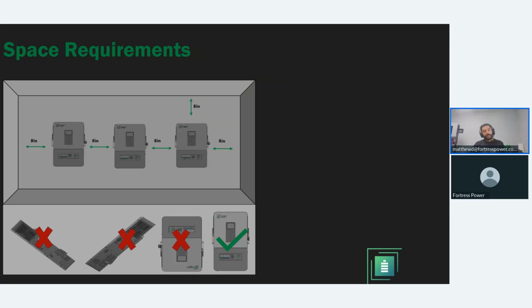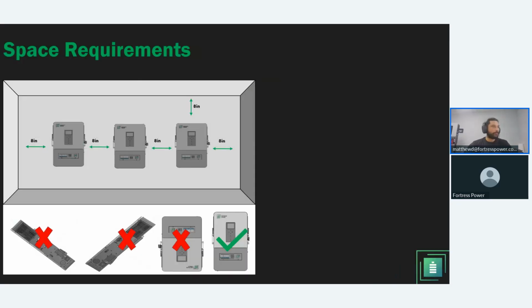All right. One thing we are going to require, and that's more for better heat dissipation, will be that each inverter is spaced 8 inches apart, assuming you're installing multiple of them. Again, reminder that you can do up to 6, but inverter to inverter spacing should be 8 inches. Inverter to wall spacing should also be 8 inches, and inverter to floor should be 8 inches, although that's more for heat dissipation. We recommend installing the inverter at eye-seeing level for sure, and a reachable level.